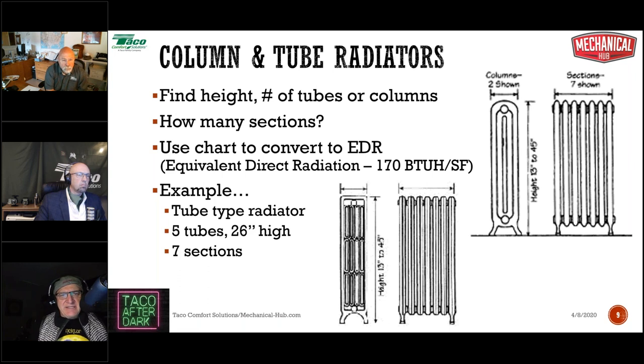Let's take a tube type radiator like this one right here. It's a five tube radiator, so there's going to be one, two, three, four, five tubes. Each section is 26 inches high, and there are seven sections in that radiator. So it's a tube type radiator, five tubes per section, 26 inches high, seven sections total. How do we convert that? How do we figure out the potential output of that radiator?